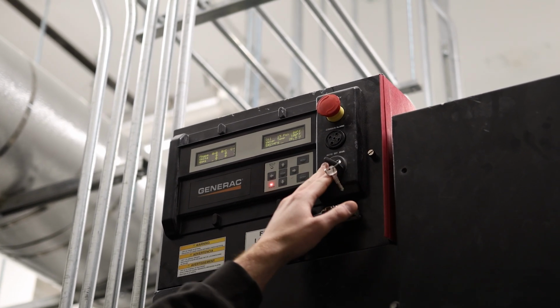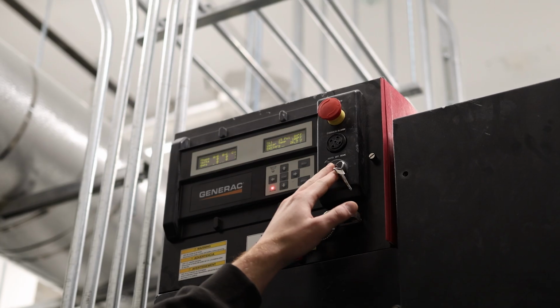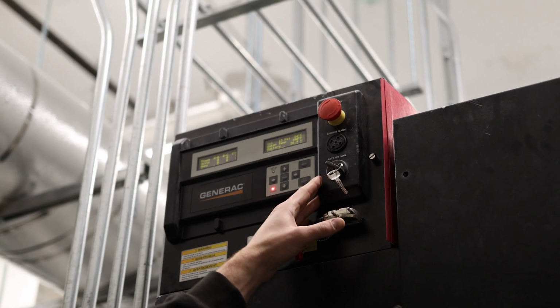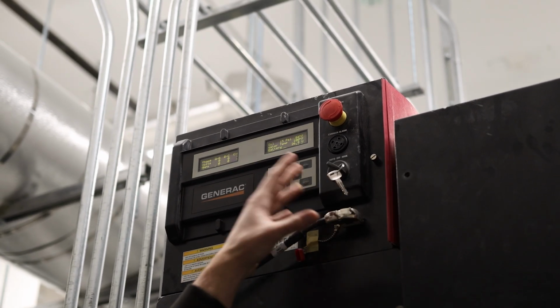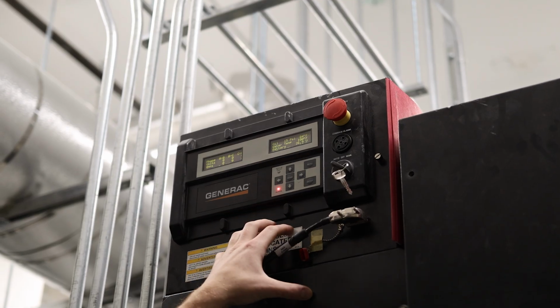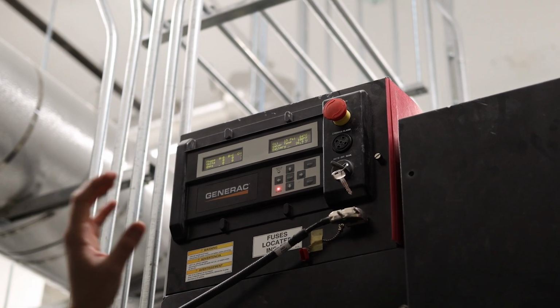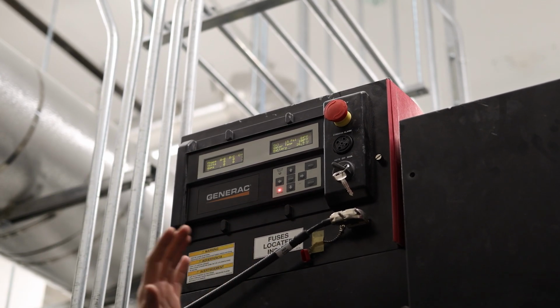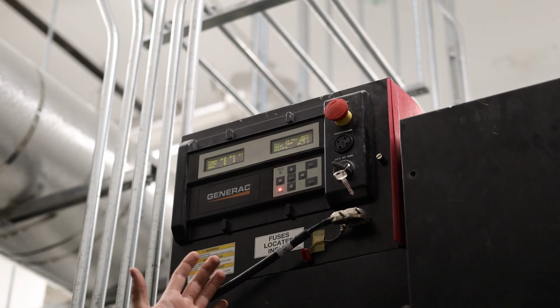The key switch is 3 positions. Automatic, off, and manual. Auto is where the key switch needs to always be in. That means it's waiting for the signal from our transfer switch to start. If it's not in auto, it's not going to run automatically.